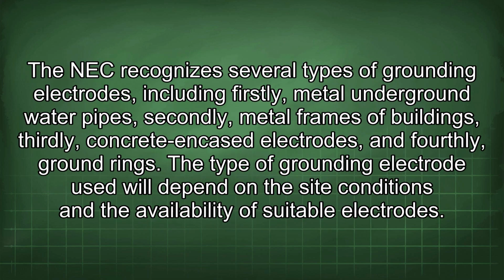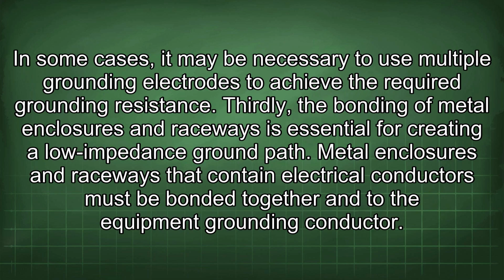Secondly, the type of grounding electrode used is also important. The NEC recognizes several types of grounding electrodes, including firstly, metal underground water pipes, secondly, metal frames of buildings, thirdly, concrete encased electrodes, and fourthly, ground rings. The type of grounding electrode used will depend on the site conditions and the availability of suitable electrodes. In some cases, it may be necessary to use multiple grounding electrodes to achieve the required grounding resistance.